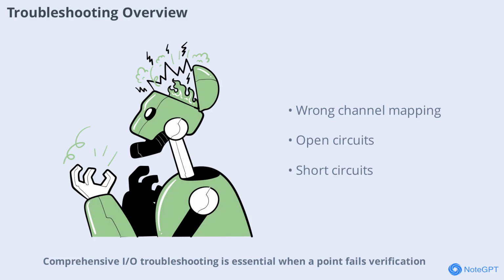Comprehensive I/O troubleshooting is essential when a point fails verification. The guide provides diagnostic steps for common issues, including wrong channel mapping, open circuits, short circuits, sensor failures, and grounding or EMI noise. Effective troubleshooting ensures that problems are quickly identified and resolved, minimizing downtime and ensuring system reliability.